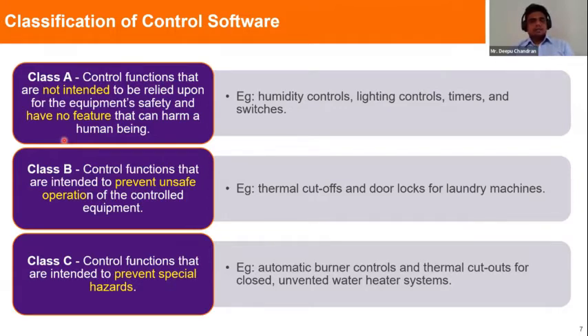And the next one is Class C, which is the highest level. These are control functions that are intended to prevent special hazards. For example, automatic burner controls, thermal cutoffs, or unvented water heater systems. So you know that in unvented water heater systems, if it is overheated, there can be a hazard and it can create harm to people, right? So that needs to be prevented. Such mechanisms, including error detection, indication, prevention or control mechanisms, need to be implemented. So these are highly critical software and they are classified as Class C software.